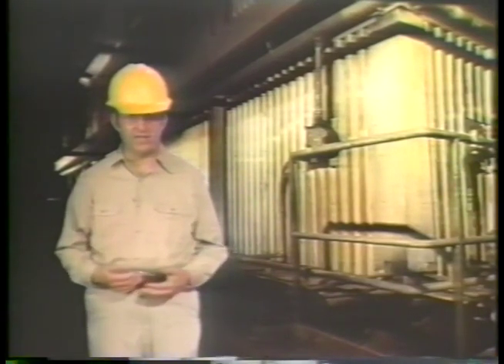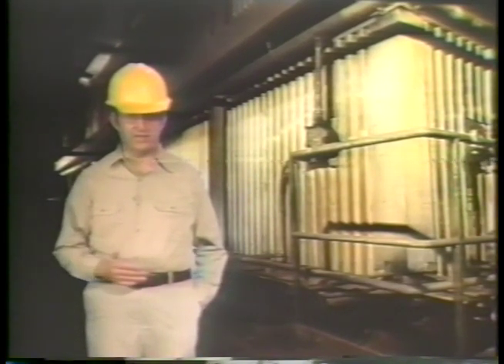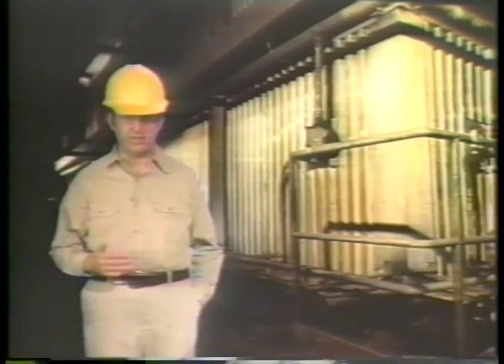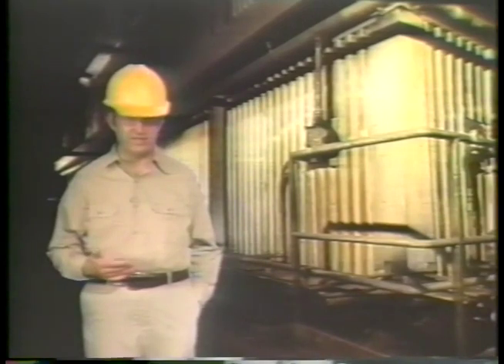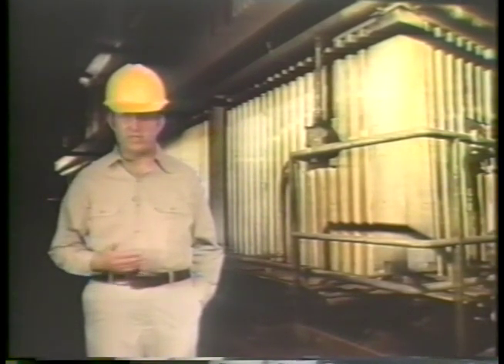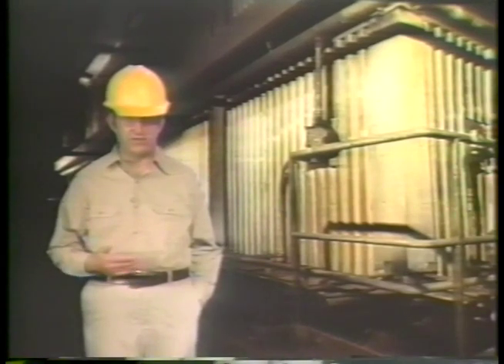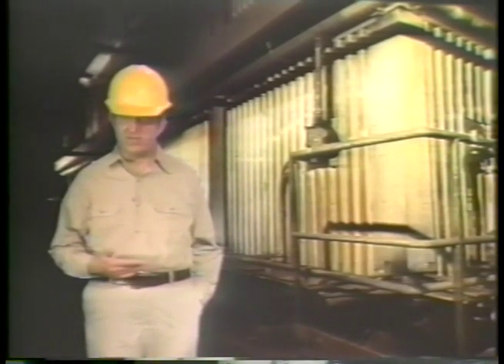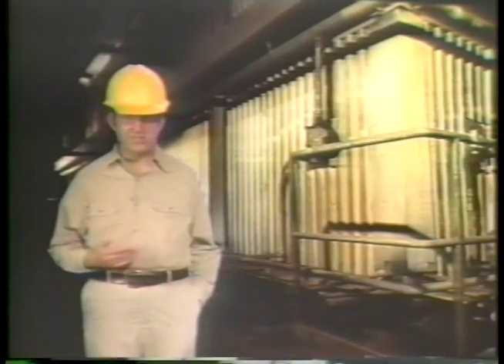It's important that you understand how the air and gas circuit increases the overall efficiency of boiler operation. Without the system described, cold secondary air would enter the wind box and delayed or incomplete combustion would take place. The resulting gases and unburned fuel produced by incomplete combustion would then travel through the boiler and out the stack, carrying with them a great deal of heat which would go to waste. Your boiler is designed to burn a specific fuel which, if mixed with the correct amount of air, will release a certain amount of radiant heat needed to generate steam. After that, the flue gases will still contain sufficient convection heat for superheating and reheating the system. By using the hot flue gas to heat superheater tubes, reheater tubes, the economizer, and the secondary air, we can utilize the heat to do work and increase the overall efficiency of the boiler.